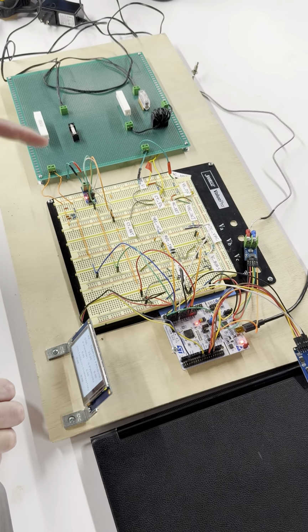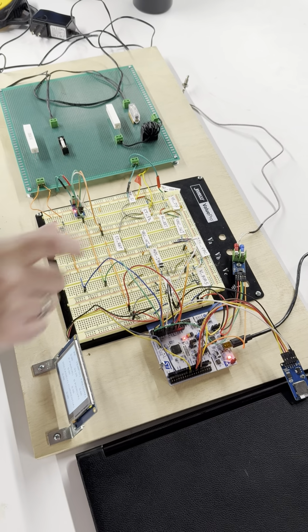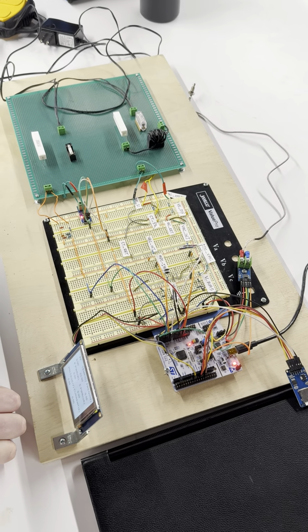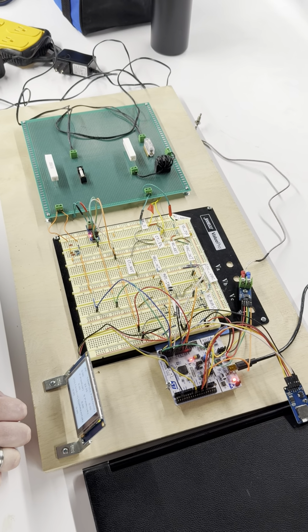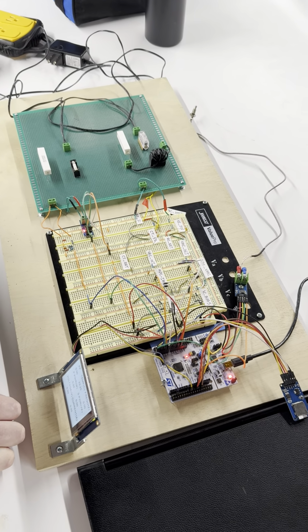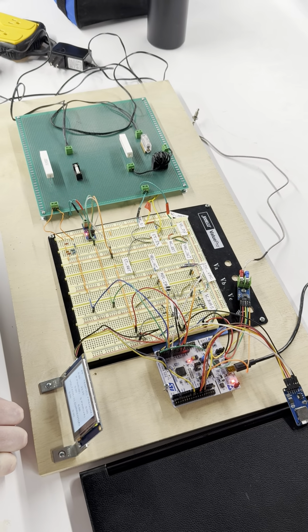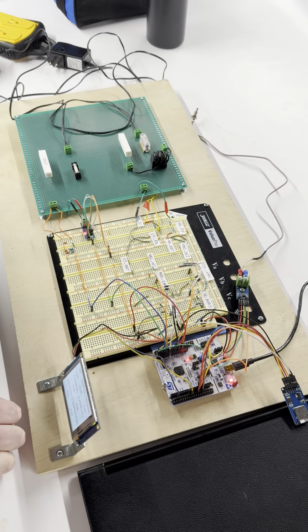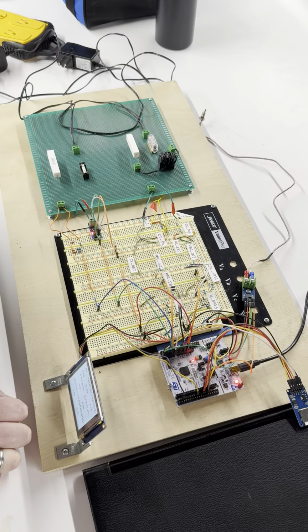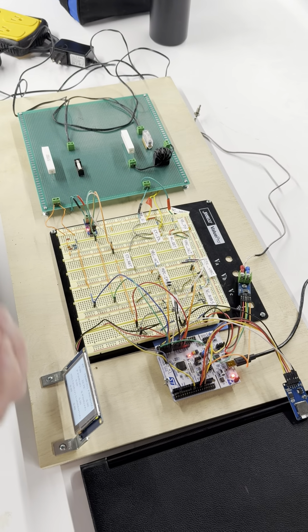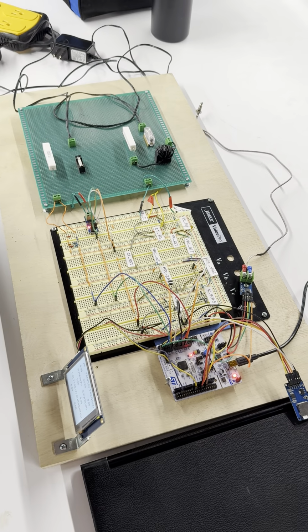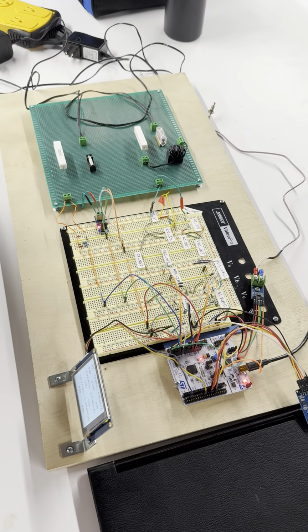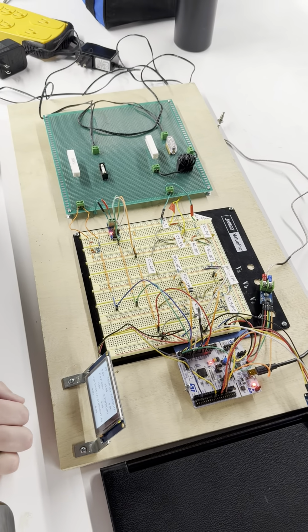The way that the current sensing circuit works, which is right here, is it is computed via a current sensing transformer with multiple primary turns to improve sensitivity at low current. The CT secondary current is converted to a voltage across a burden resistor. And then finally, the loop current is calculated through several different factors: the voltage across the burden resistor, the number of turns, the CT ratio, and a small calibration constant.